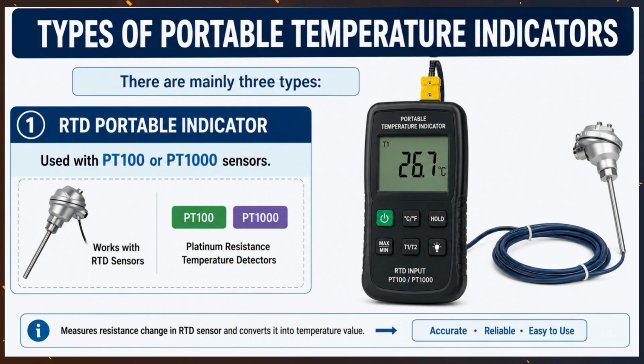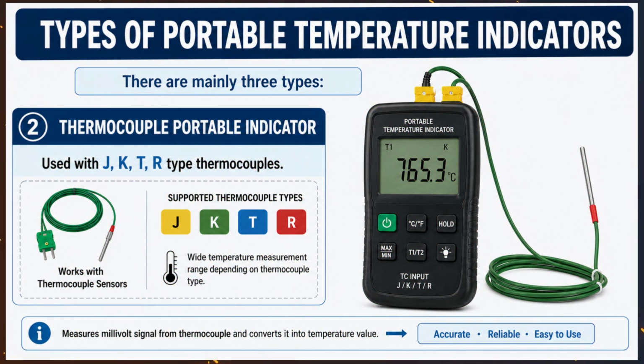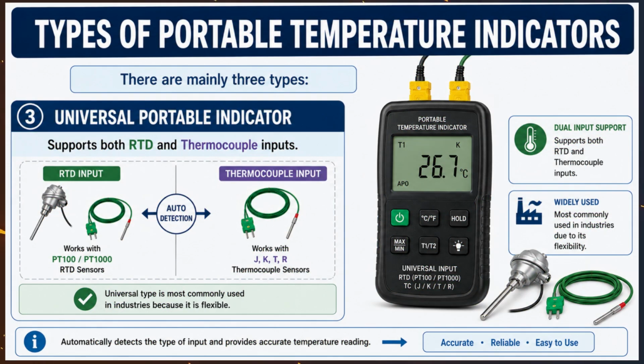Types of portable temperature indicators. There are mainly three types. First, RTD portable indicator used with PT100 or PT1000 sensors. Second, thermocouple portable indicator used with J, K, T, R type thermocouple. Third, universal portable indicator supports both RTD and thermocouple inputs. Universal type is most commonly used in industries because it is flexible.